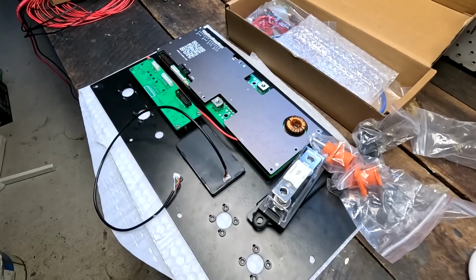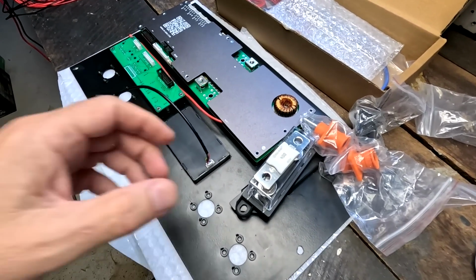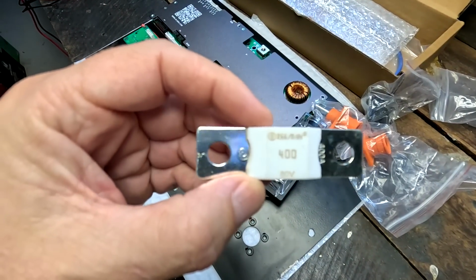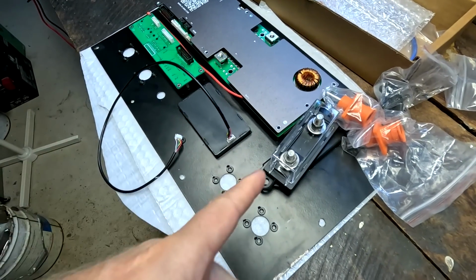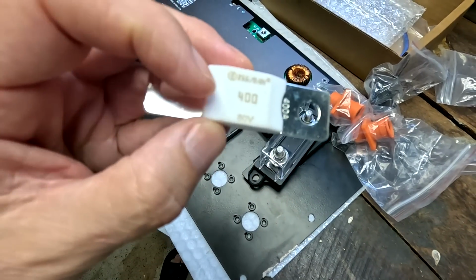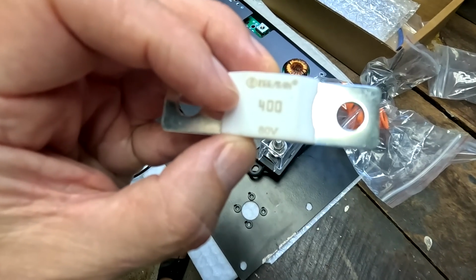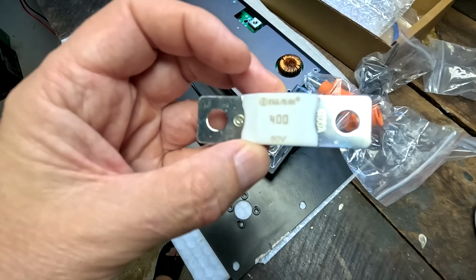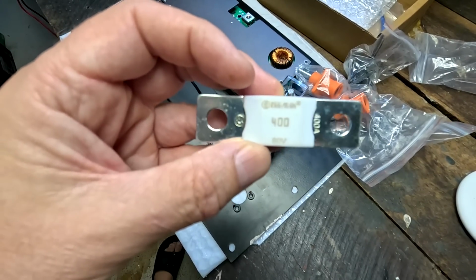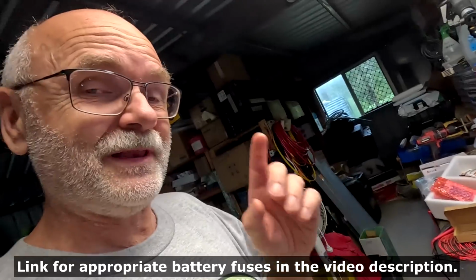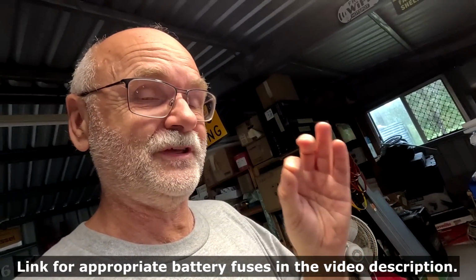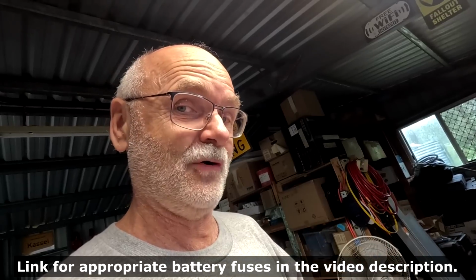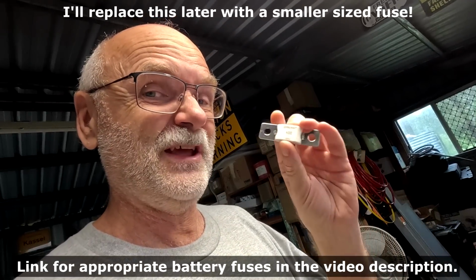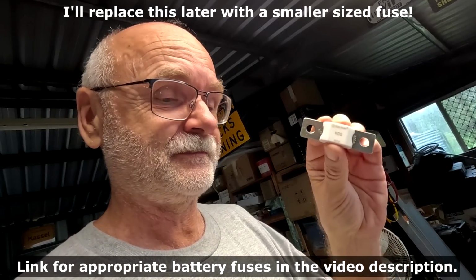Woo! And now you think, wait a minute, Andy, 400 amp fuse, that's a bit too much for this BMS and all the cabling you probably install. This would mean like a double 70 square mil cable at least, maybe even double 95 square millimeter. We will have an external circuit breaker for this battery here, which limits the current to 80 amps only, so this is only for direct short protection.